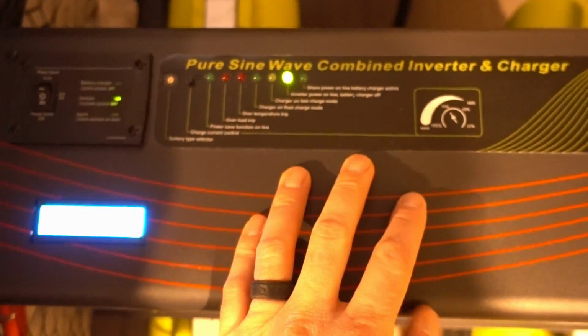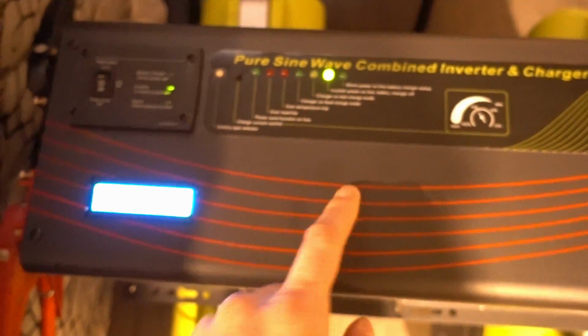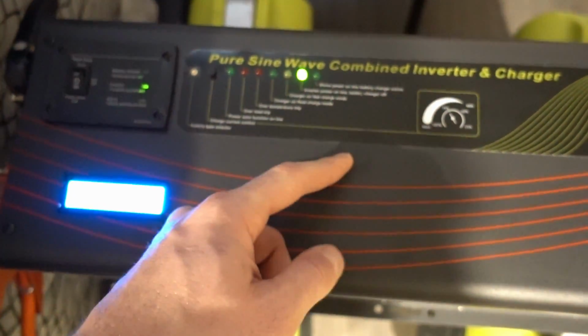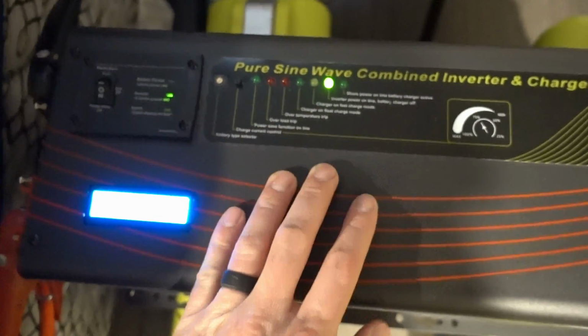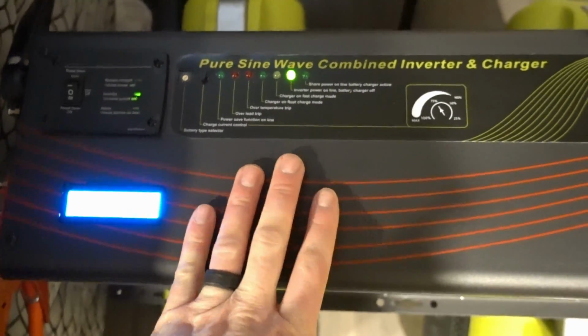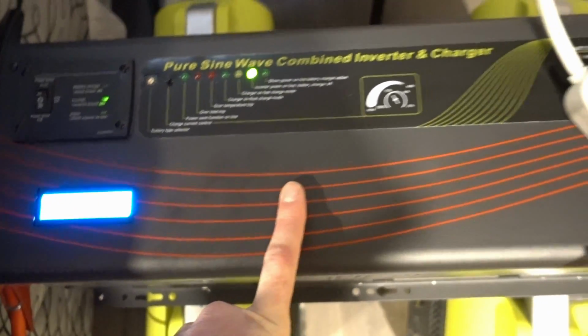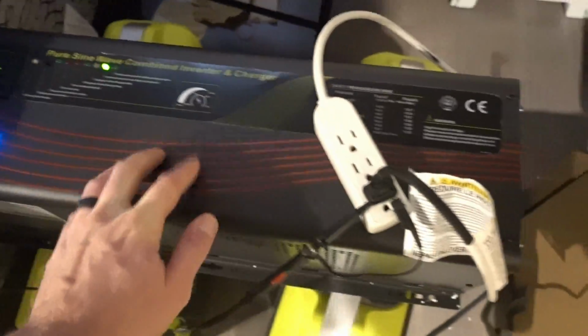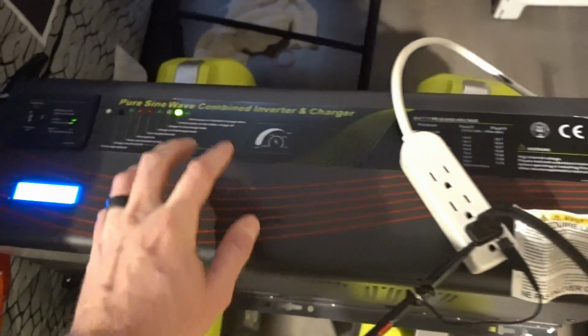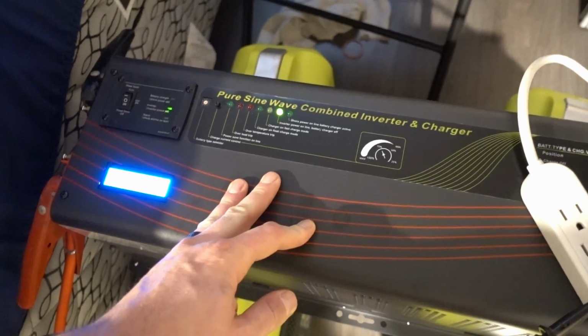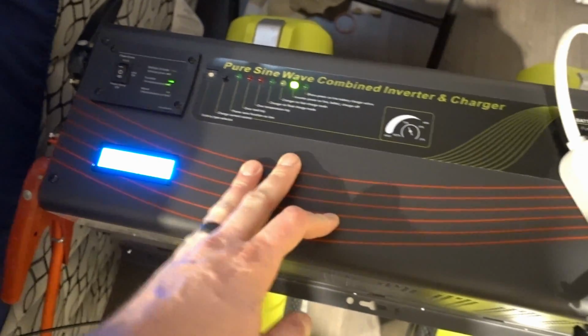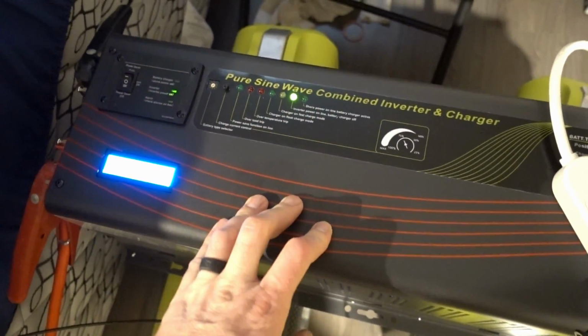It is 6,000 watts, but it probably can only do 3,000 watts continuous on one side, 3,000 watts continuous on the other side. 240 is 6,000 watts continuous. And its peak, I'm guessing, I have to talk to the manufacturer, it probably can peak one side at about 9,000 watts on both sides, and then I believe it peaks 18,000 watts on the 240 for a few seconds.